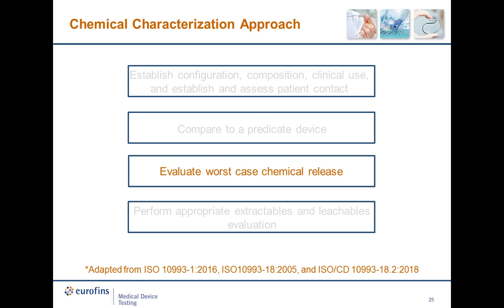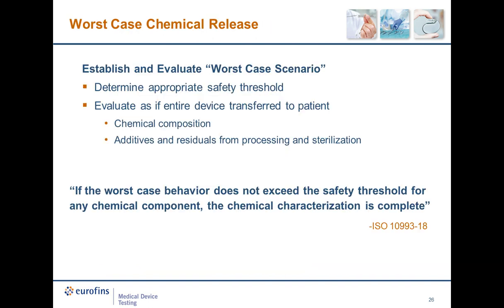If a sponsor cannot establish that their device has an equivalent or less than equivalent safety risk than an established device, the next approach the standard directs a sponsor to consider is a worst-case chemical release. The basis of the worst-case chemical release is evaluating the impact if the entire device transferred to the patient during use. The first step in performing this evaluation is determining the appropriate safety threshold. The safety threshold is based on the threshold of toxicological concern, as well as the patient contacting and dosing information. I will describe how to determine a safety threshold in more detail when I discuss extractables and leachables evaluation.